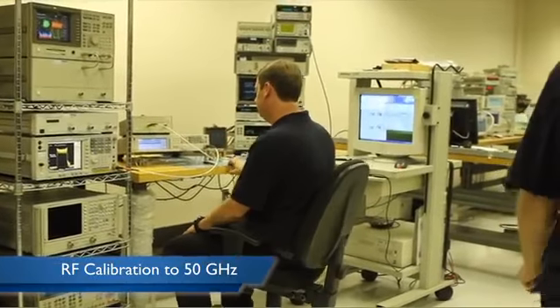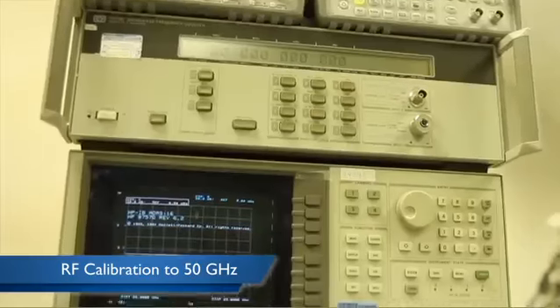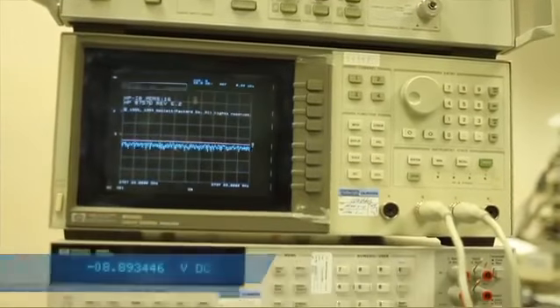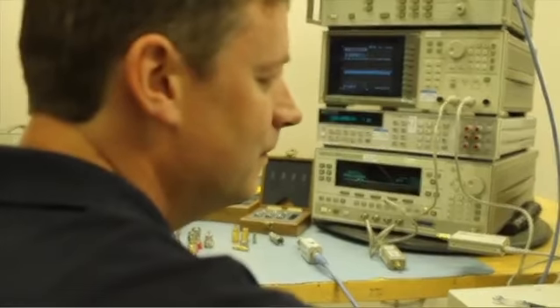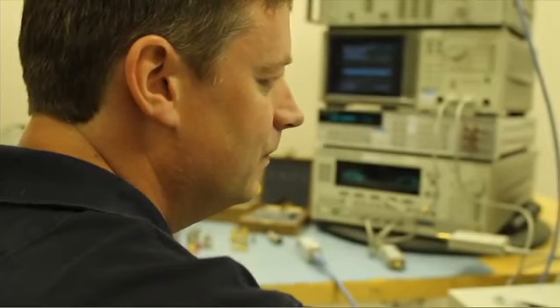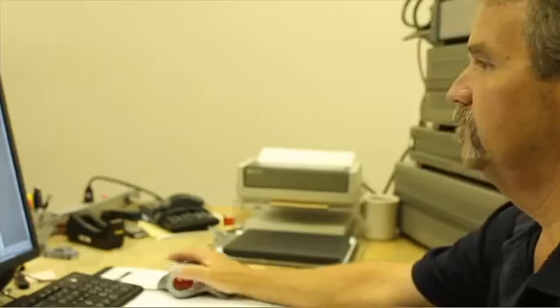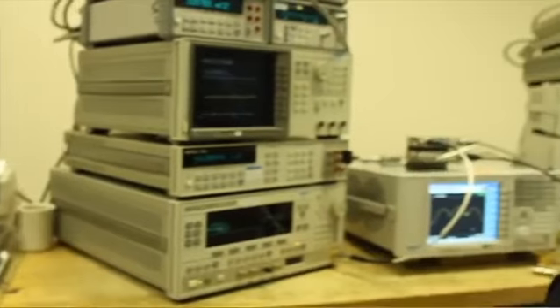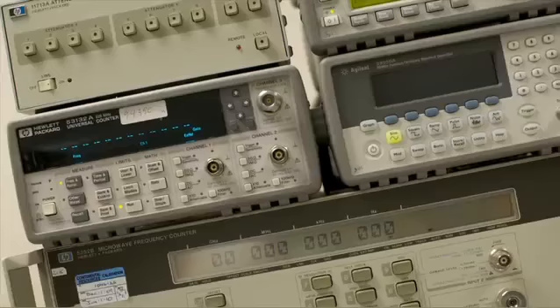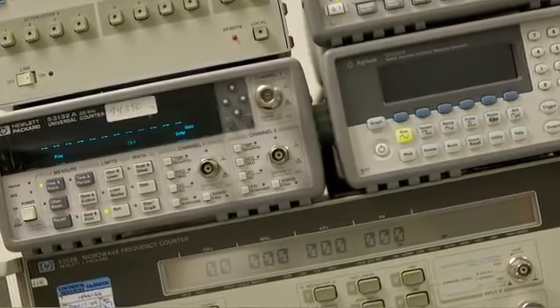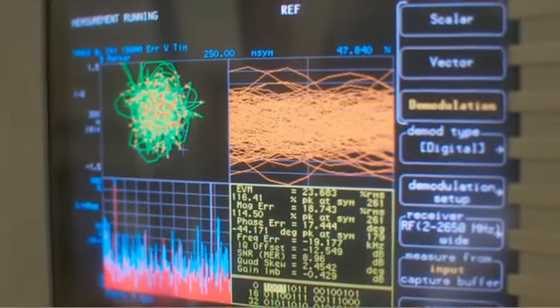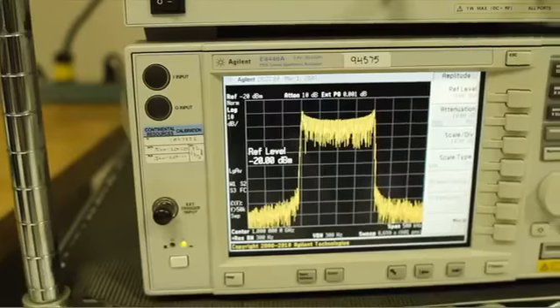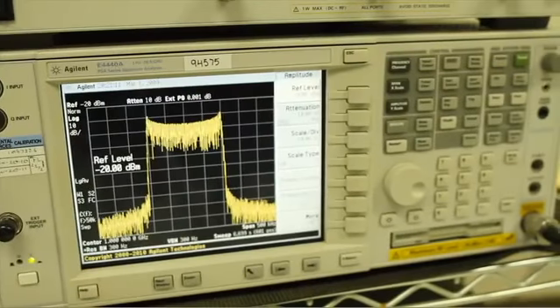One of our cal stations is a RF bench where we have the capability to calibrate test equipment up to frequencies of 50 gigahertz. We have a lot of automation in those stations to be able to do calibrations computer controlled. One of the reasons for that is repeatability. It cuts out human error when you're making measurements and also documents the test results.